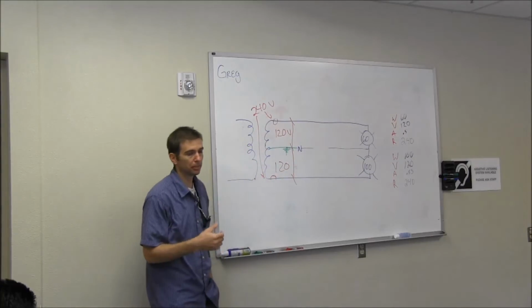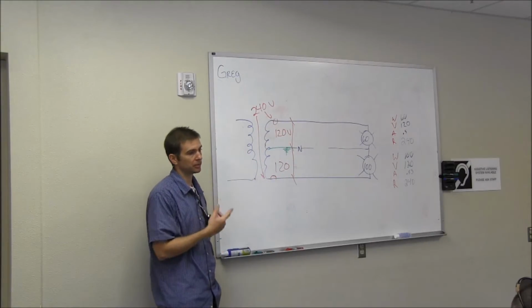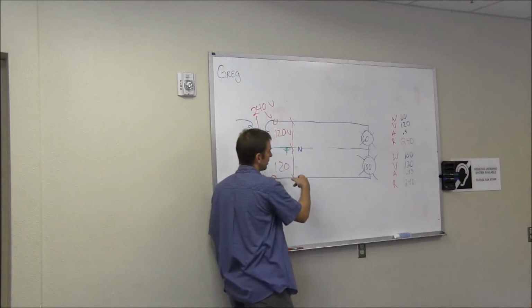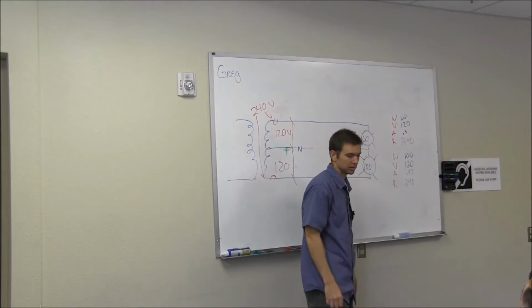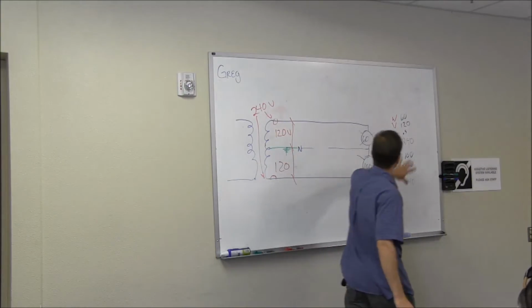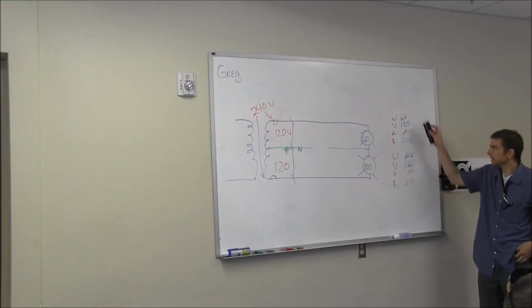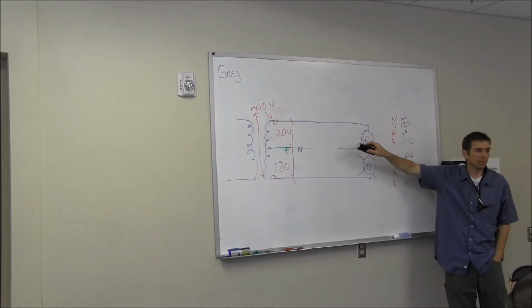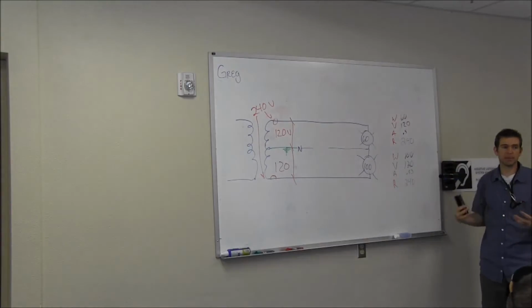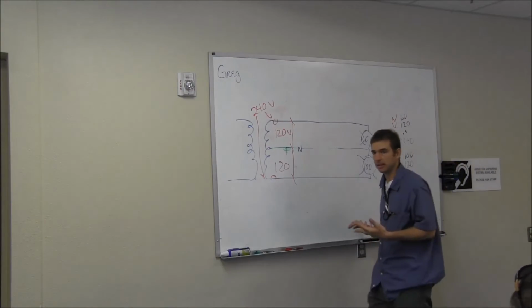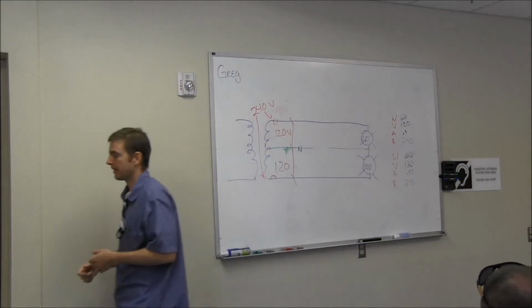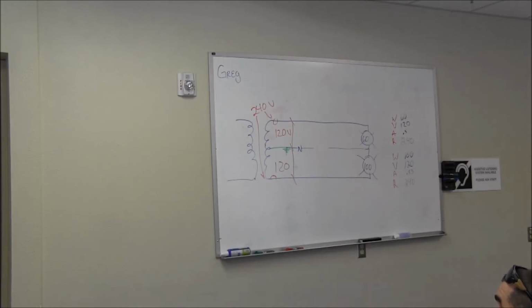My hope is that the breaker trips, but sometimes the breaker doesn't trip. And when you lose a neutral, sometimes the breaker doesn't trip, but your field values change. Now we've just changed our values here by opening up our neutral. These were our previous values when the circuit was working properly. Once that neutral came apart, and sometimes it's accidental, not just a field failure. If I'm opening up this light switch, and there's a white wire, a red wire, a blue wire, and a black wire all coming into the switch, and then I have the regular lighting, but I have a three-phase multi-wire branch circuit coming in from the panel.